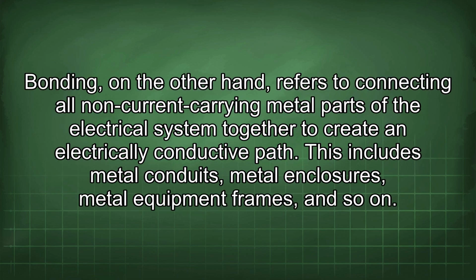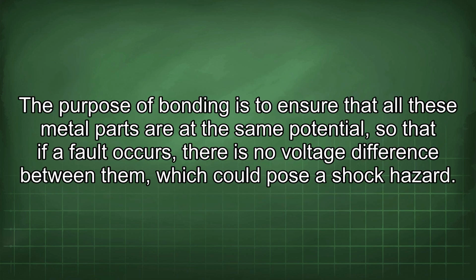Bonding, on the other hand, refers to connecting all non-current carrying metal parts of the electrical system together to create an electrically conductive path. This includes metal conduits, metal enclosures, metal equipment frames, and so on. The purpose of bonding is to ensure that all these metal parts are at the same potential so that if a fault occurs, there is no voltage difference between them, which could pose a shock hazard.